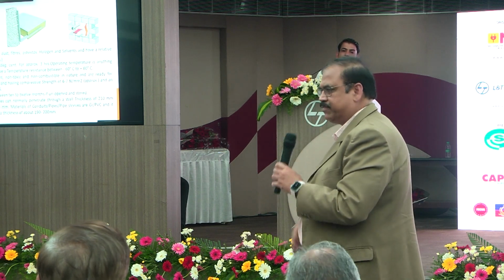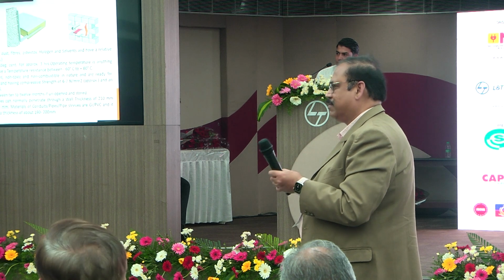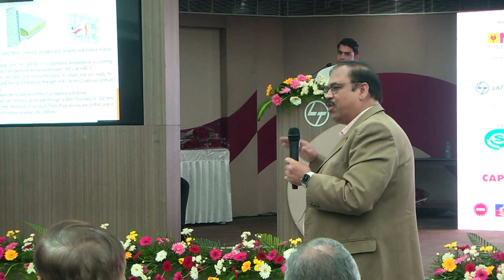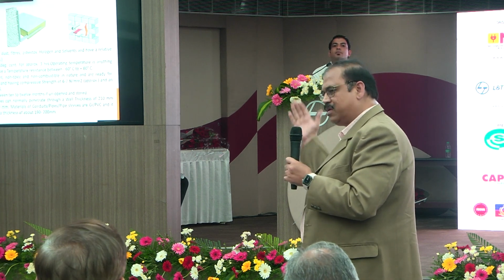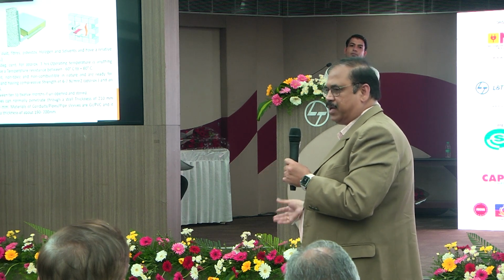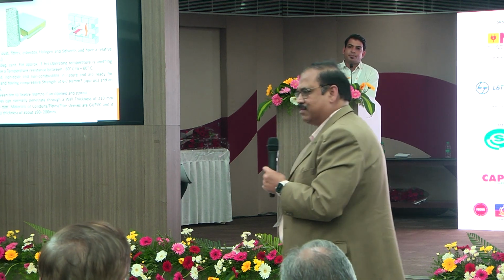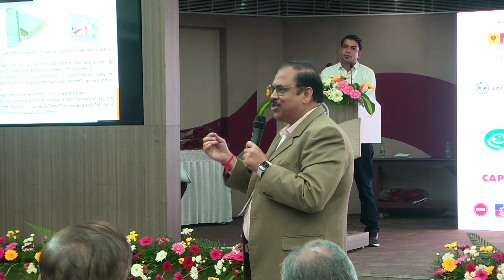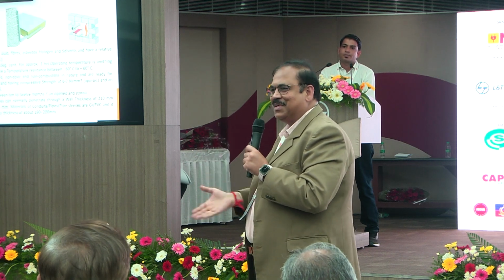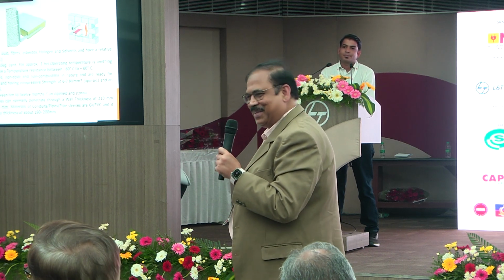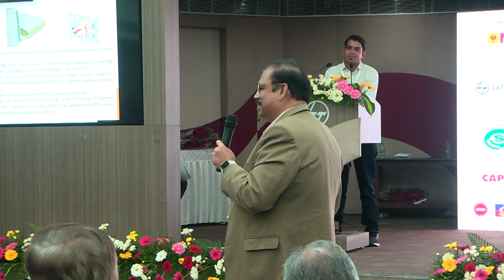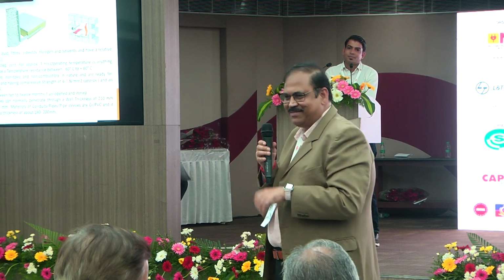Use that coating. Where you are not using fire survival cable, this is an alternative to that. But your point is right. There is no point applying only on the top. It should be for the full cable all around. That way, I think it should be an installation practice.